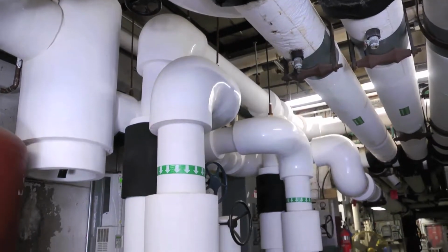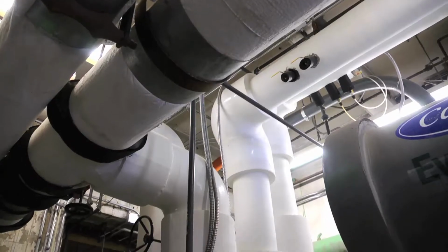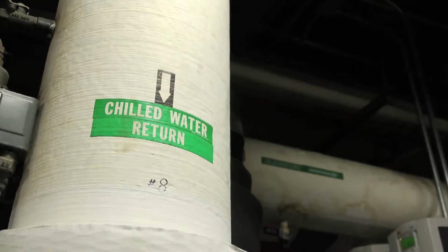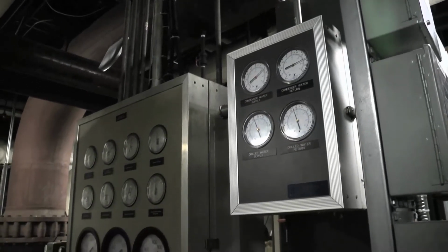And the root of it is, we have these infrastructures that we have to keep updated in order for patient safety to be maintained. It resulted in a piping renovation where we were cutting out different aspects of the piping system and replacing those with more efficient systems that corrected a lot of the hydraulic issues they were experiencing. And they had a single chiller well beyond its useful life, really no capital plans to replace that, although they knew the replacement had to take place.